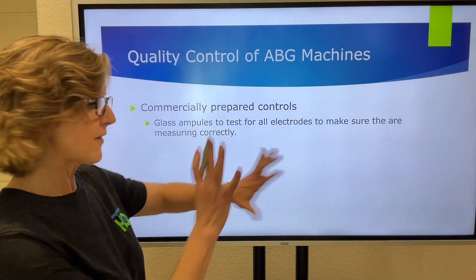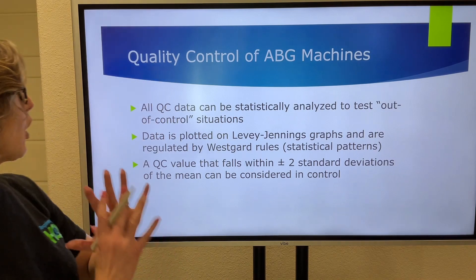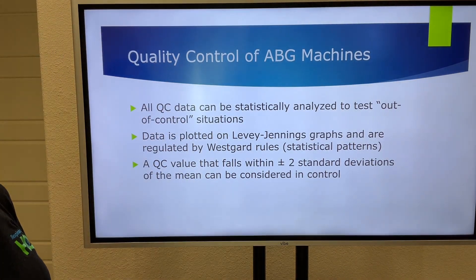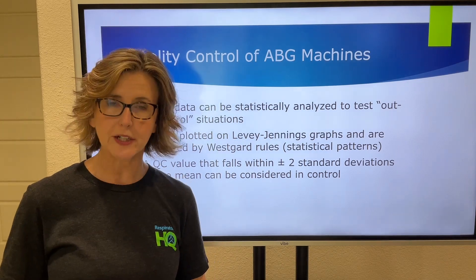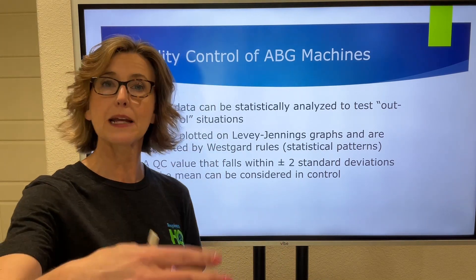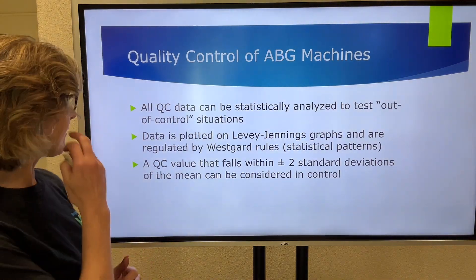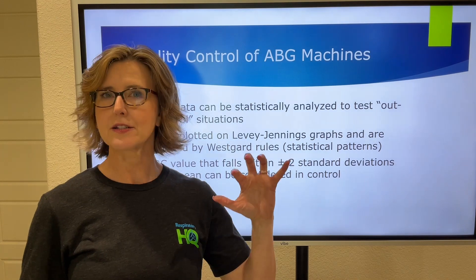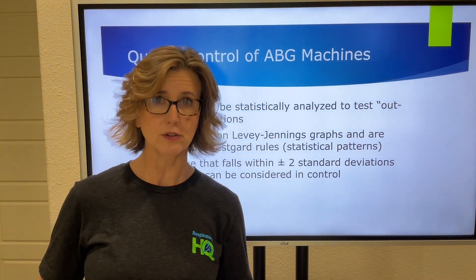All of this data — whether it's one-point calibration, two-point calibration, or commercially prepared controls — can be plotted on a statistical chart called a Levy-Jennings report. We statistically analyze it to see if there are any out-of-control situations, because if we have an out-of-control situation, we can't trust that blood gas and can't turn in any exam results for clinical decision-making. This data is plotted on the Levey-Jennings graph, and these graphs are regulated by something called Westgard rules — named after the man who developed them — which are statistical patterns you need to know.